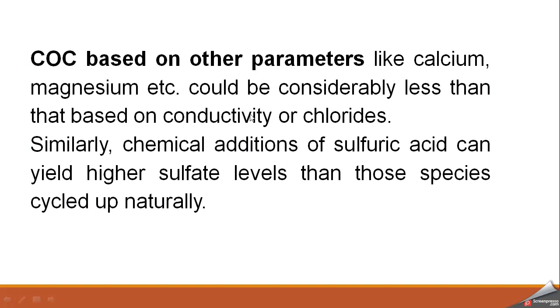Because conductivity reflects the total amount of minerals dissolved in the water, or you can say the ions present in the form of completely dissolved ions, or chloride, because chloride is also very highly soluble in the water. However, in the case of calcium and magnesium, the calcium and magnesium ions present in the makeup water and in the blowdown will not normally concentrate in a similar ratio.